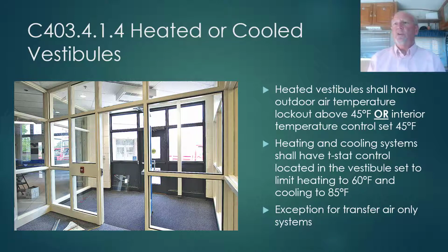And so there's been a change in the code that requires control of those tempering systems. If you install a heating system in the vestibule, let's say an electric wall heater or an overhead radiant heater, then you shall have a control on that that locks out that piece of equipment if it's above 45 degrees outdoor temperature, or it is controlled by an interior temperature control set to 45 degrees. So you need a thermostat that can be set no higher than 45, or you can control that through an outdoor air lockout, perhaps through a DDC building automation system.